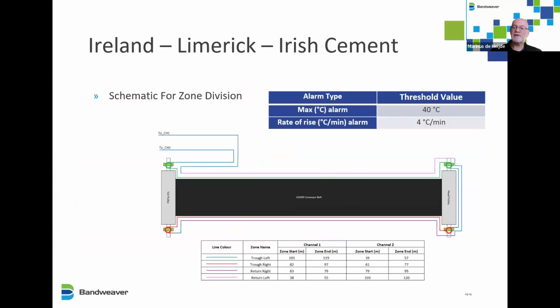And again, different alarm settings here, with a maximum alarm quite low at 40 degrees and a rate of rise alarm at 4 degrees per minute. And lower in the slide here, you can see the zone starts and zone endings for channel 1 and channel 2.